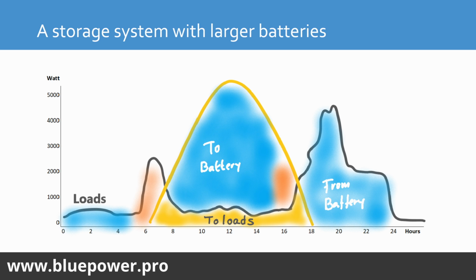But if it's connected on the AC output 2, it will disconnect as soon as there's a power failure as well. But you can configure the AC output 2 relay to stay on depending on battery SOC, as long as those loads combined don't exceed the output power of the inverter.